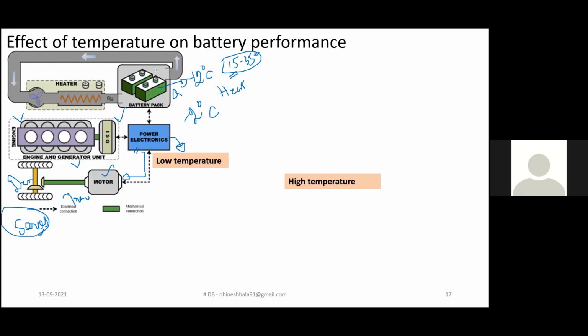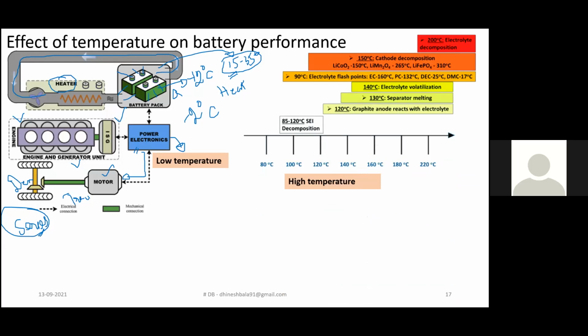If you look at this pictorial representation, you will have an air blower. This air is allowed to pass through a heater and the hot air is exposed to the battery pack. This hot exposure would raise the temperature of the battery pack, and more or less we will try to attain the desired temperature limit of 15 to 35. So this would be the case when you are dealing with the low temperature condition. And talking about high temperature condition, we are very much aware that the safety limit would vary from 60 to 70 degrees Celsius for the lithium based batteries.